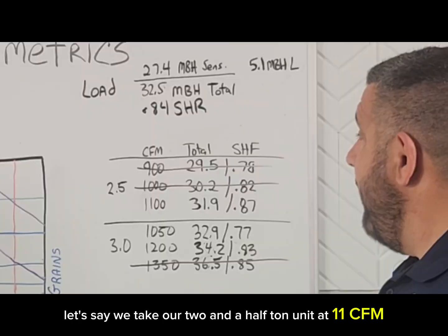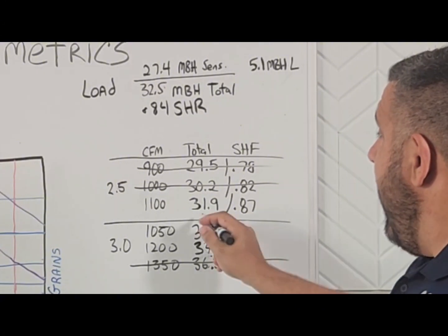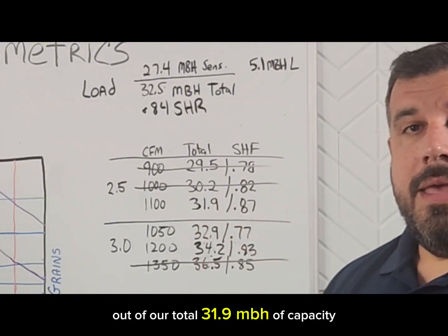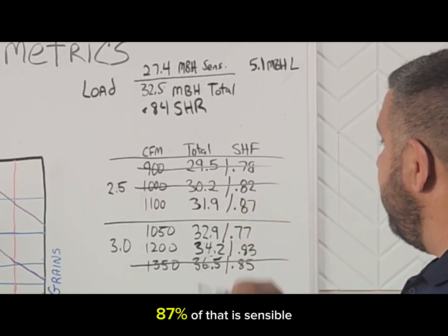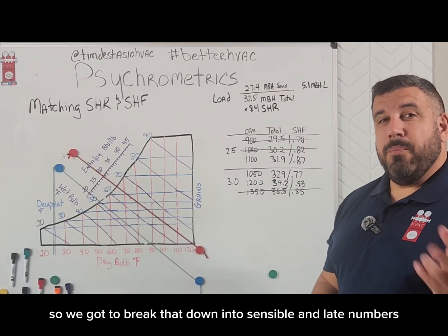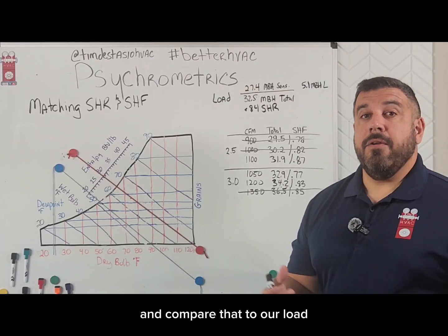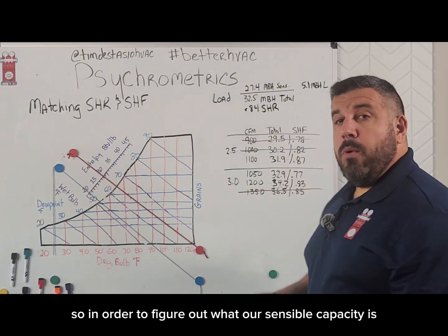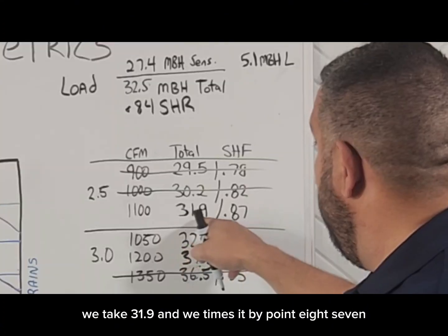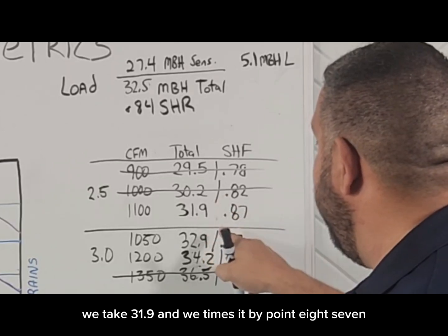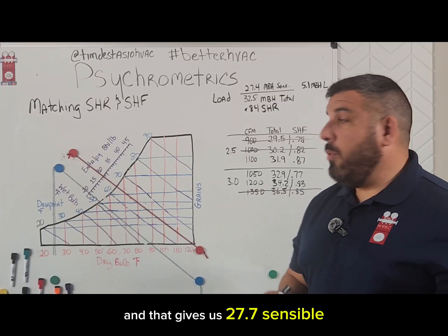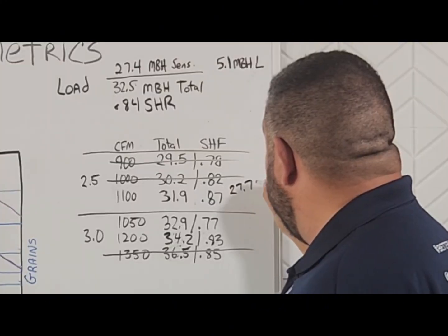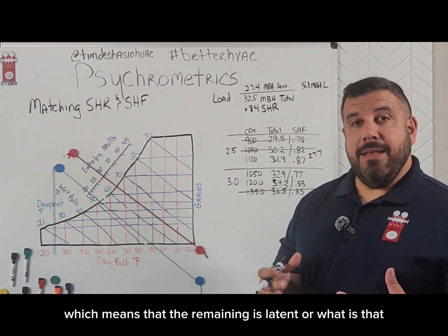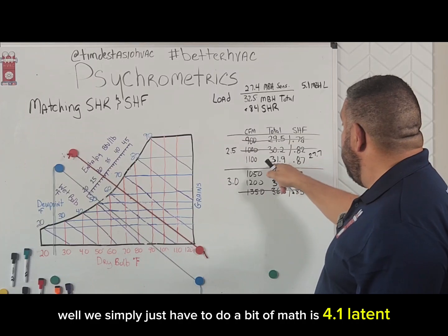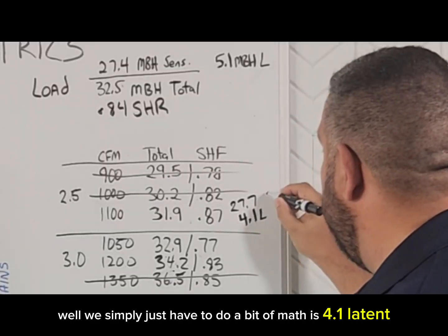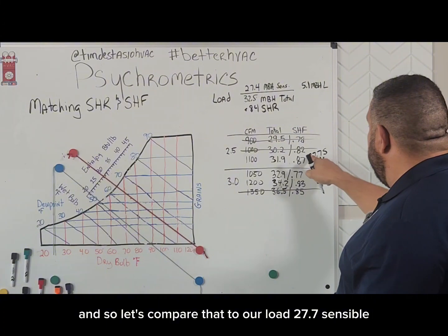Let's say we take our 2.5 ton unit at 1100 CFM. Out of our total 31.9 MBH of capacity, 87% of that is sensible. So we've got to break that down into sensible and latent numbers and compare that to our load. To figure out our sensible capacity, we take 31.9 and multiply it by 0.87, and that gives us 27.7 sensible, which means the remaining is latent. We simply do a little bit of math. It's 4.1 latent.